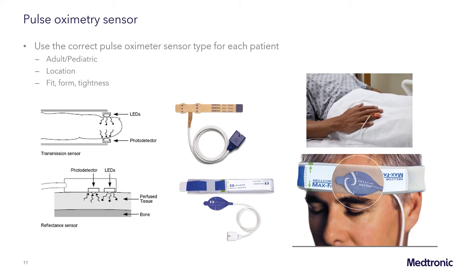It's important that the correct pulse oximeter sensor be used for each type of patient, meaning adult patients should have adult sensors, pediatric patients have pediatric sensors, that the location of the sensor be appropriate for the type of probe used, and that the probe properly fit, have good form, and be at the proper tightness in order to function properly.